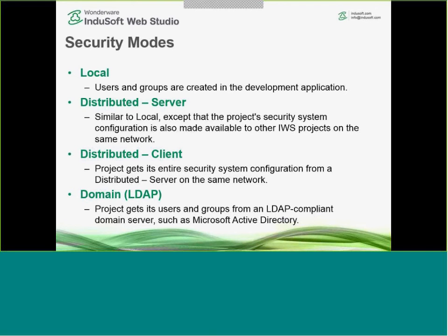If you have more than one instance of InduSoft Web Studio running on a network, then what you can do is configure one of those instances to have a fully configured user ID and group password database, and then the other instances of InduSoft on the network can basically share that database, and you only have to administer the one machine. So local, distributed server, and distributed client are more or less the same, just with the added feature of sharing the user ID, password, and group database.